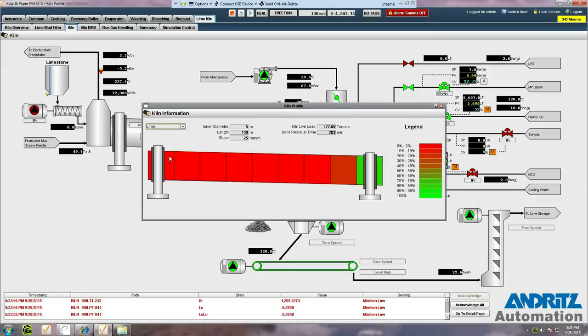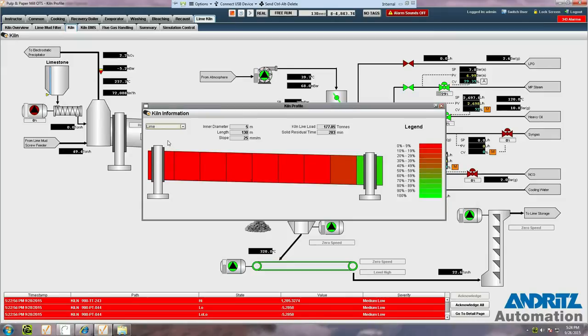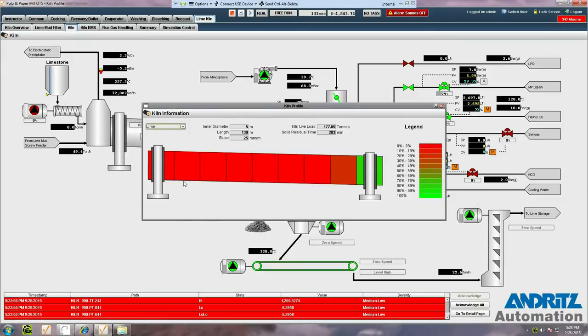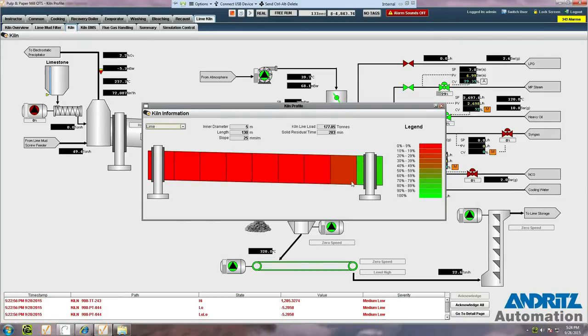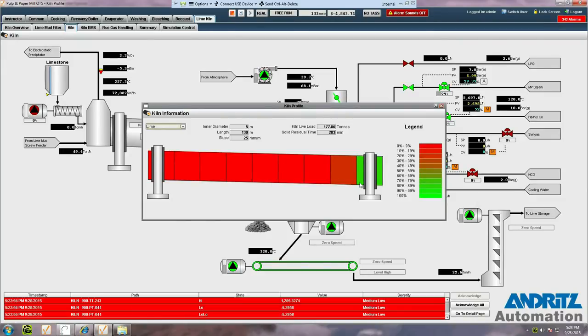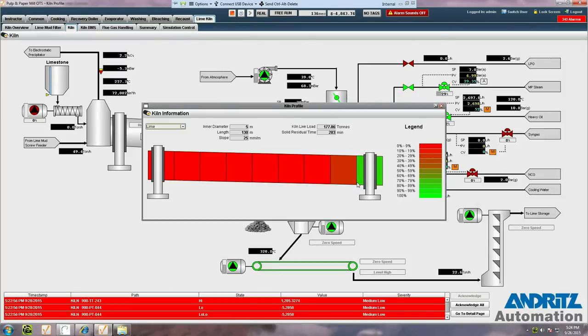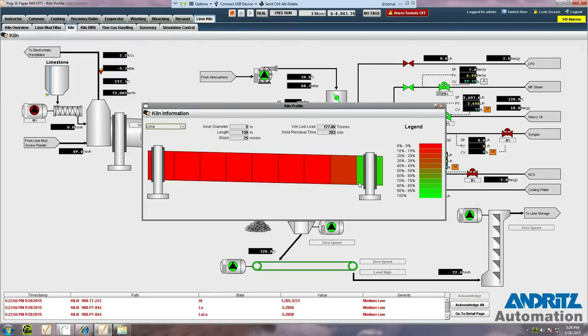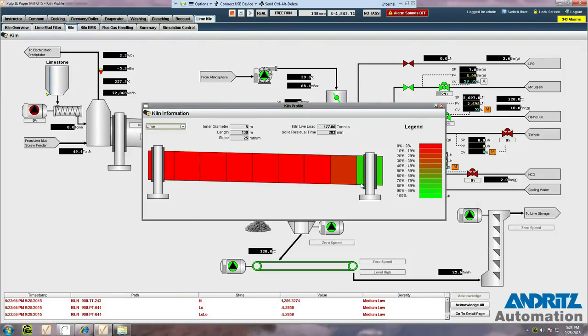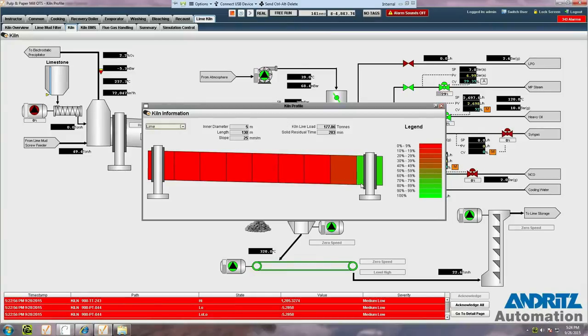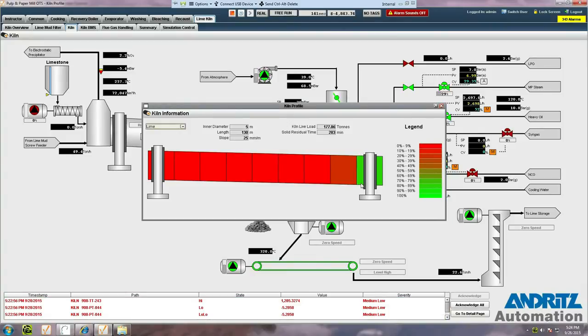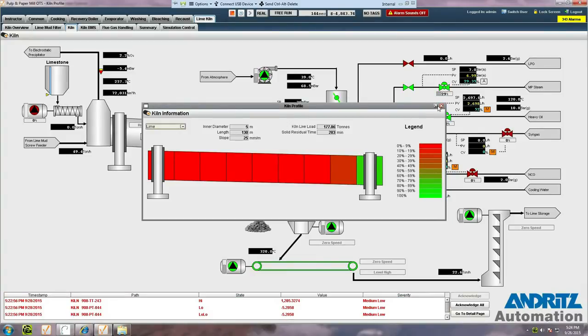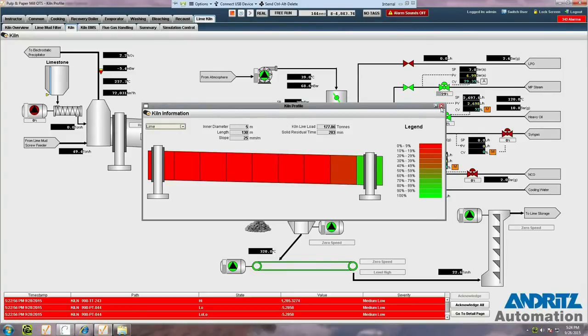We can even see the degree of the chemical reaction inside the kiln, and you can see here that calcination is actually just beginning to proceed towards the discharge end of the kiln, as this snapshot was saved in a very early warm-up state of the kiln startup process.